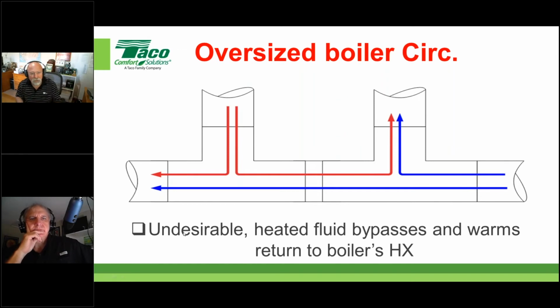What we're getting is an undesirable effect. When we take the water I just heated up and send it back across the top of these two sets of this tee right here, it's going to blend, and it's actually going to warm up the water returning to the boiler heat exchanger, which in a condensing boiler is kind of a no-no.